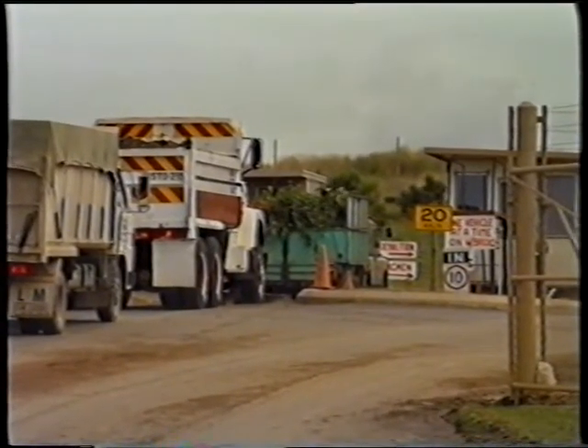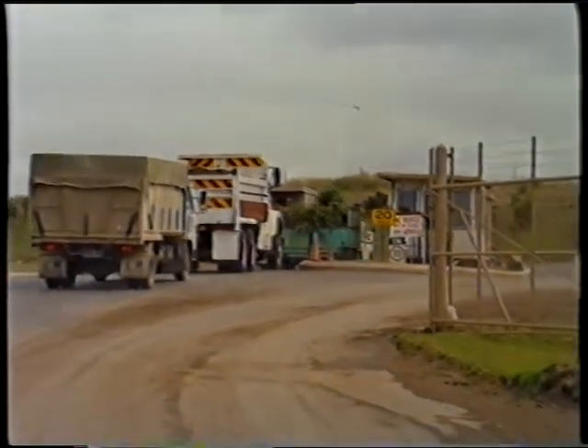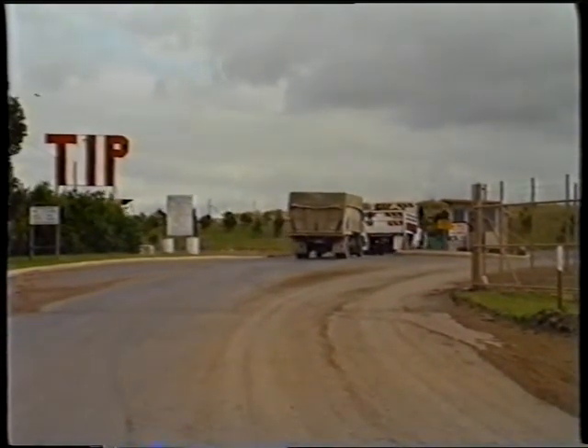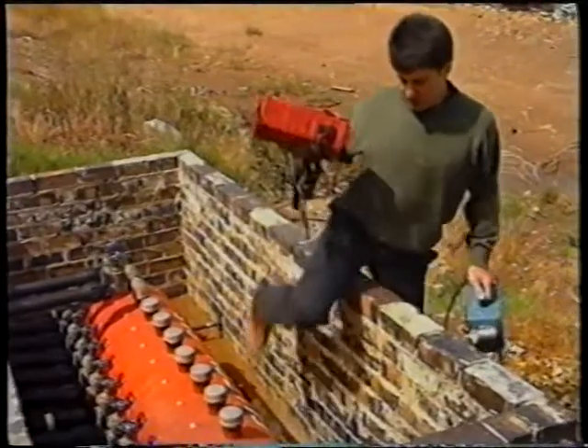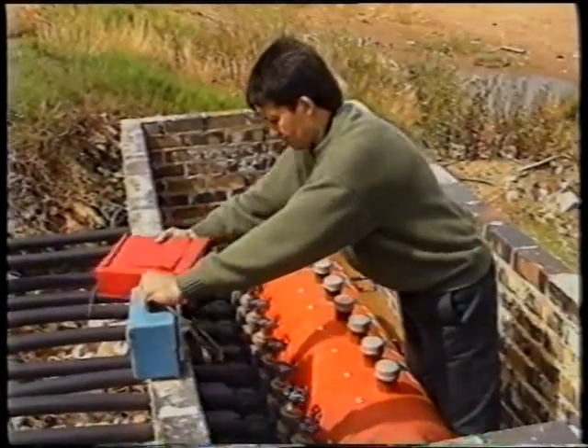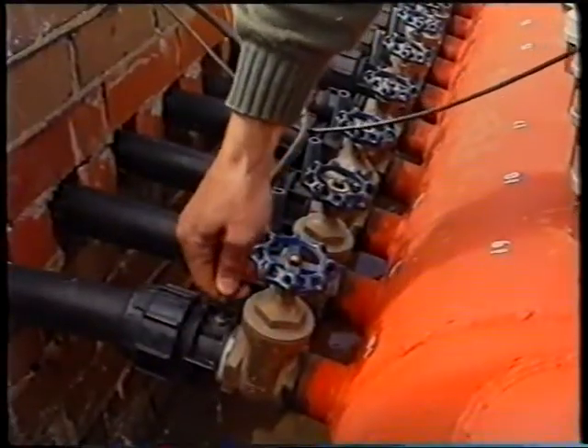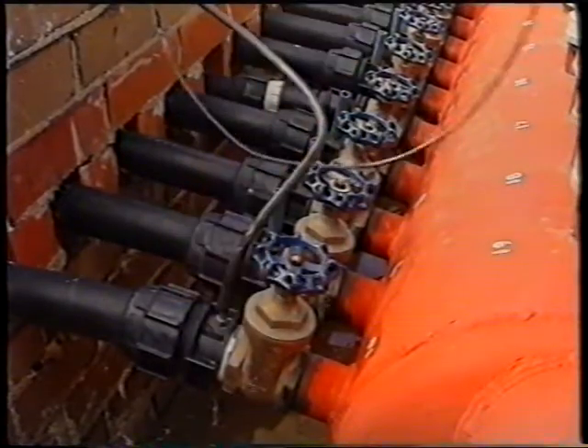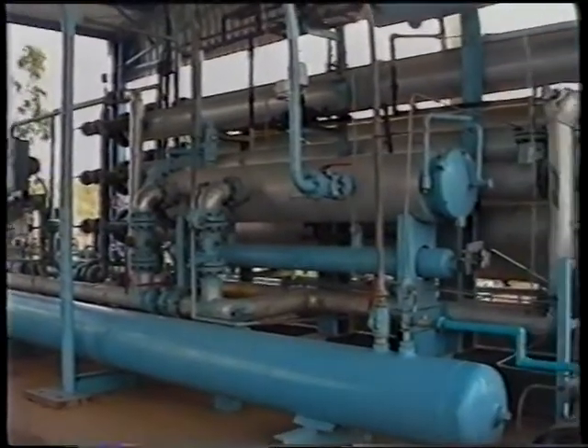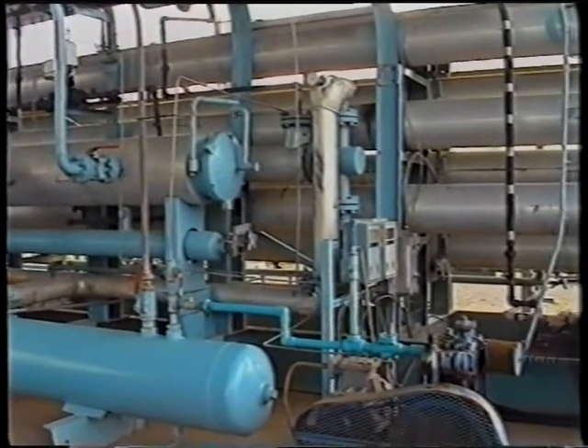Having developed expertise in the field of landfill gas, the family then sold the brickworks to start a new venture, the extraction of gas from Adelaide's largest landfill tip at Wingfield, the site of the proposed multifunction polis. Although electricity generation was the Falzons' preferred option for the use of the gas, the relatively low price for electricity offered by the South Australian Electricity Company meant that it was decided instead to sell the purified gas to the state gas utility. After researching techniques in the United Kingdom and the United States, the Falzons decided to use a membrane separation technique, which removes the carbon dioxide from the gas.